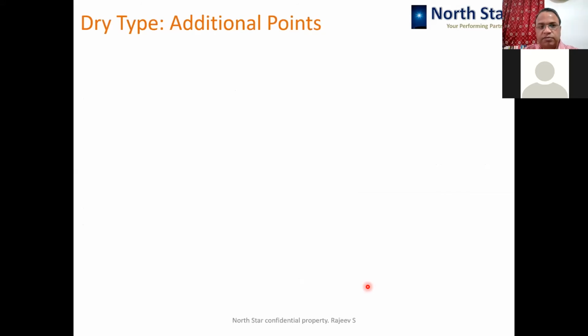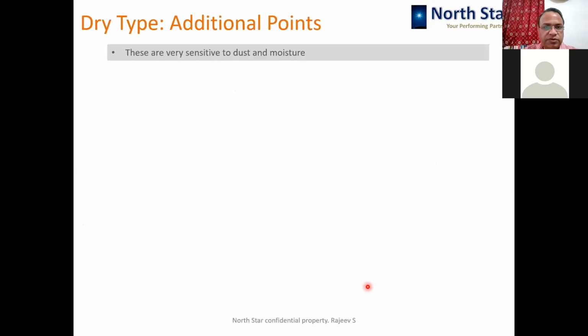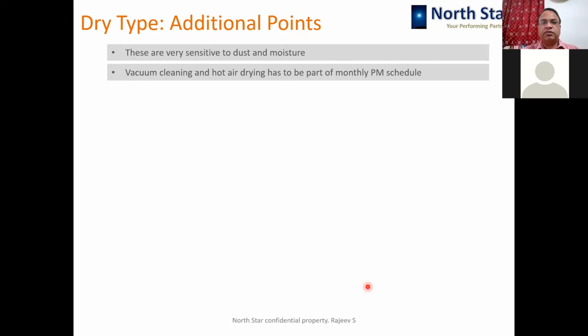Okay, there are some additional points about dry type transformers. Dry type transformers are very sensitive to dust and moisture, especially when the enclosure is ventilated type. So adequate care is to be taken in terms of vacuum cleaning and hot air drying. Okay, it can be in your monthly PM schedule.